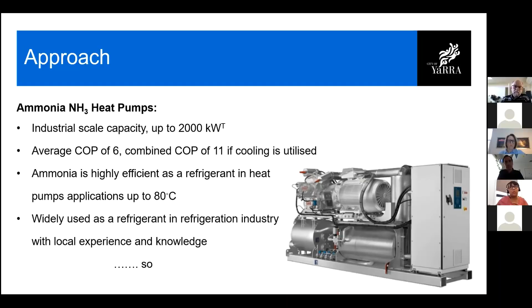So we decided to use that for the study and demonstrate its feasibility for aquatic centers, particularly showcasing its seasonal COP, because the coefficient of performance changes with ambient temperature, and that's why we always hear that argument of, are they viable in cooler climates, or are they viable in Victoria? But that's exactly what we wanted to showcase: yes, even on the coldest day and hour here, there is still plenty of heat for the heat pump to use. We wanted to use only air as a heat source, so that was a worst case scenario.